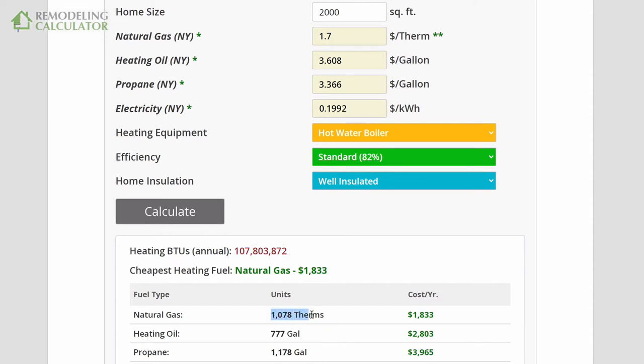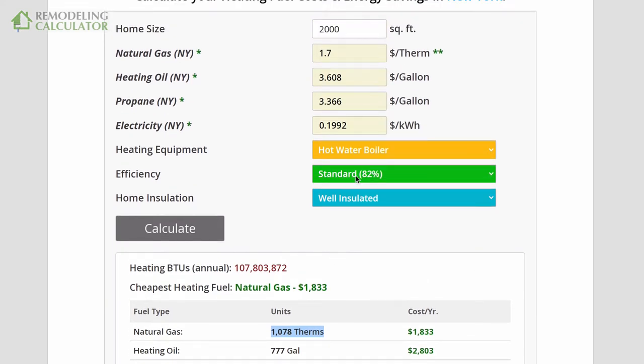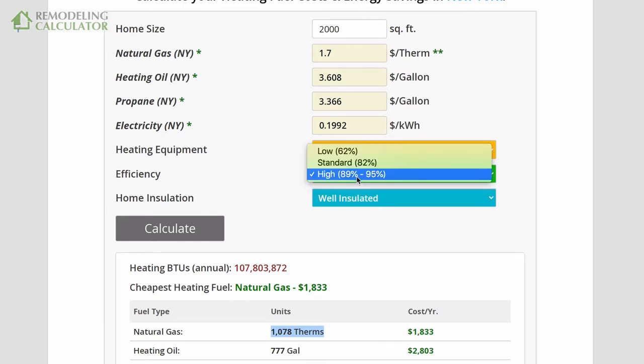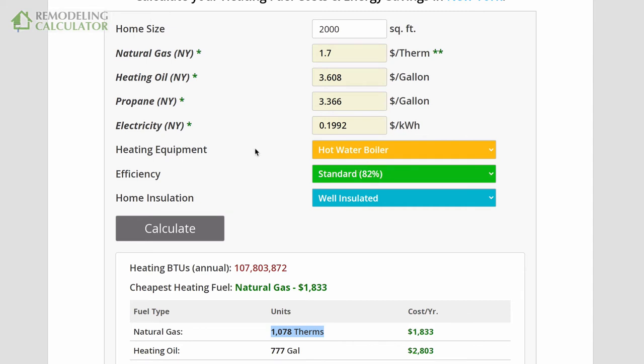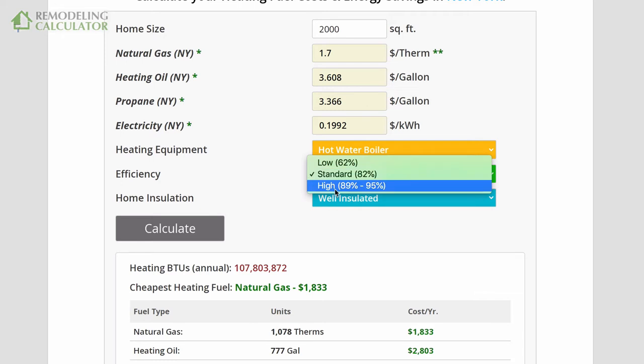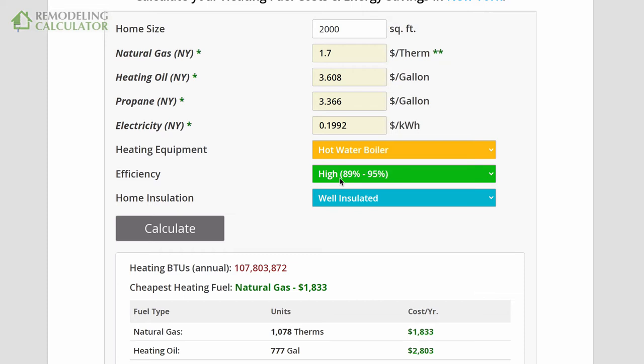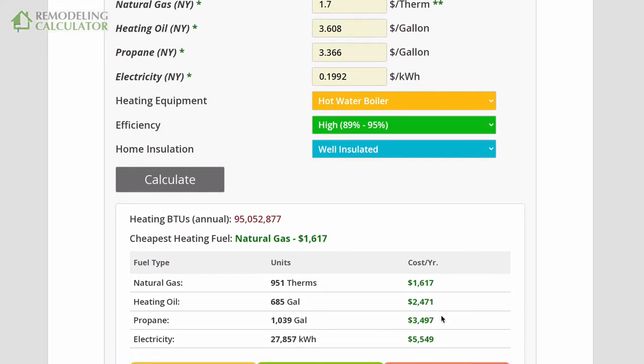You can see if you want to upgrade to a more efficient system. Most hot water boilers — and note that boilers here assume forced hot water, not steam, since steam is also less efficient. If you go with 90–95% efficiency, that is a condensing boiler. Those run only on natural gas, not oil. So the oil price shown is of no value if you're considering a condensing boiler — it only runs on natural gas, and maybe propane in some cases.